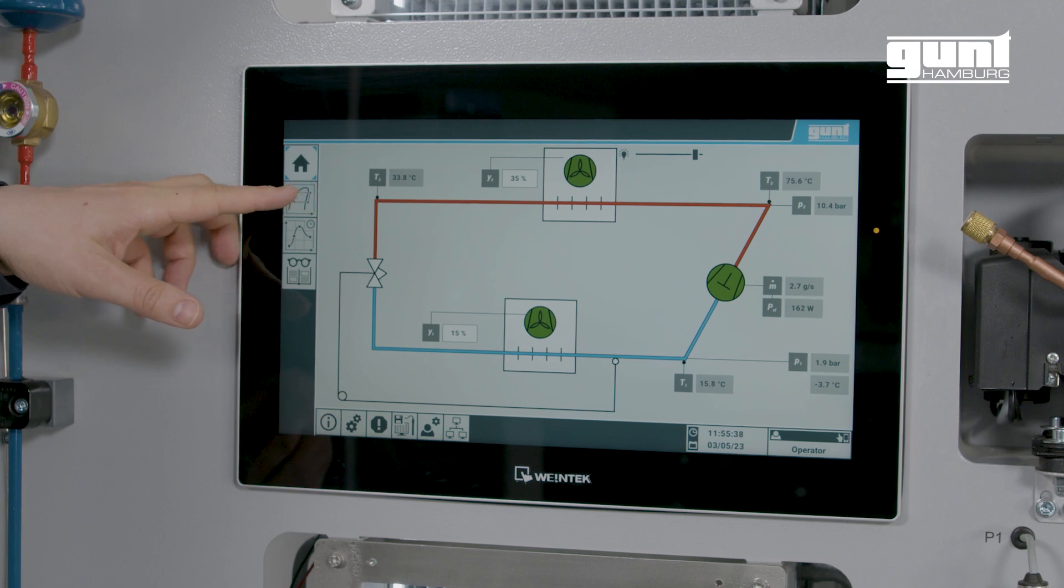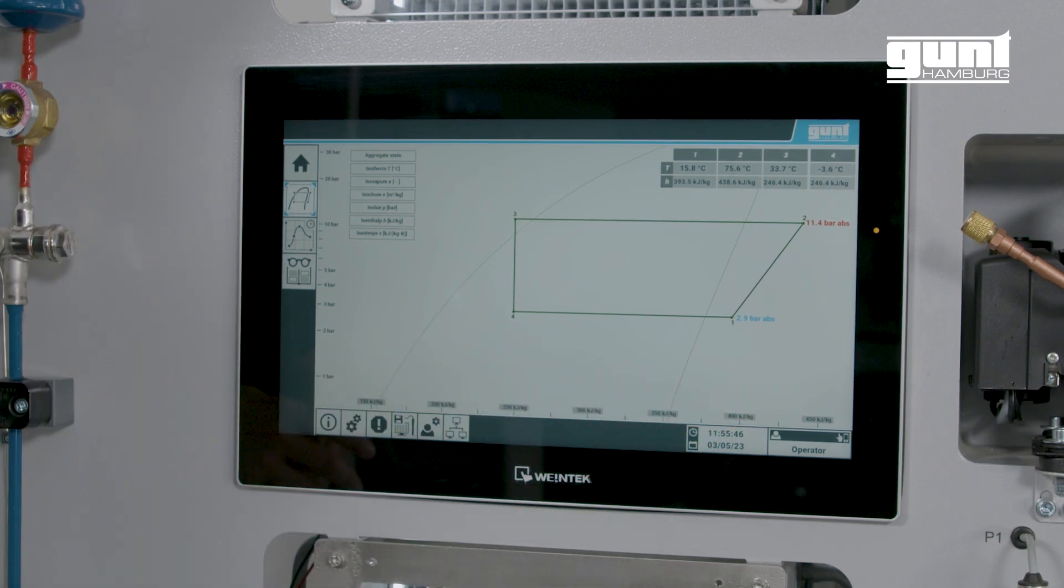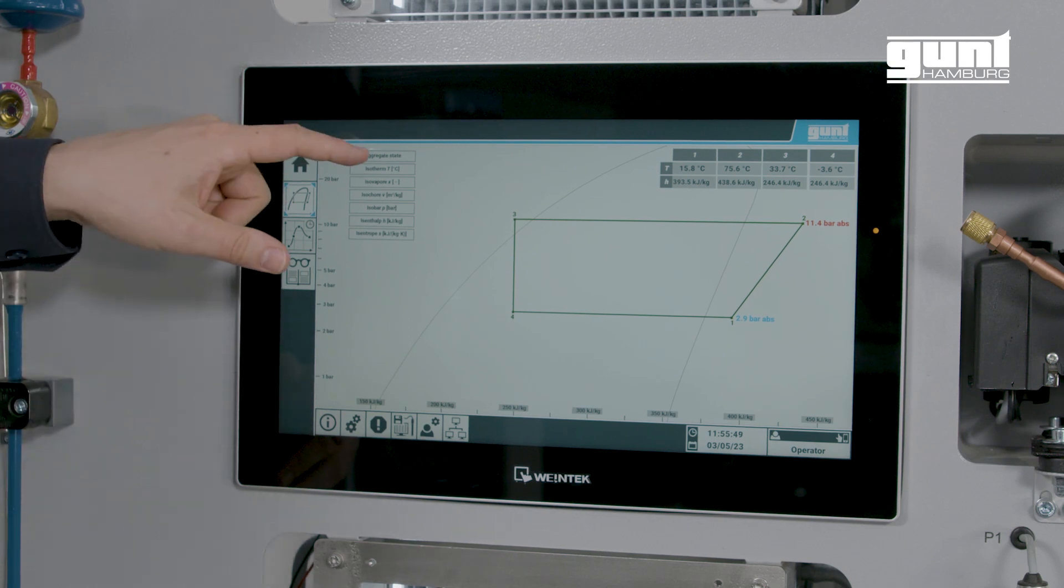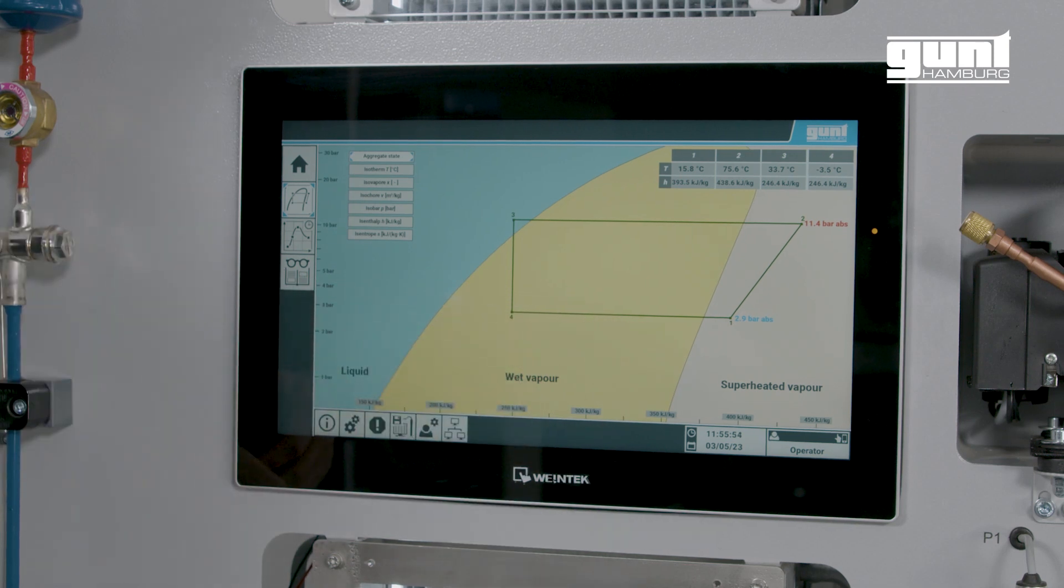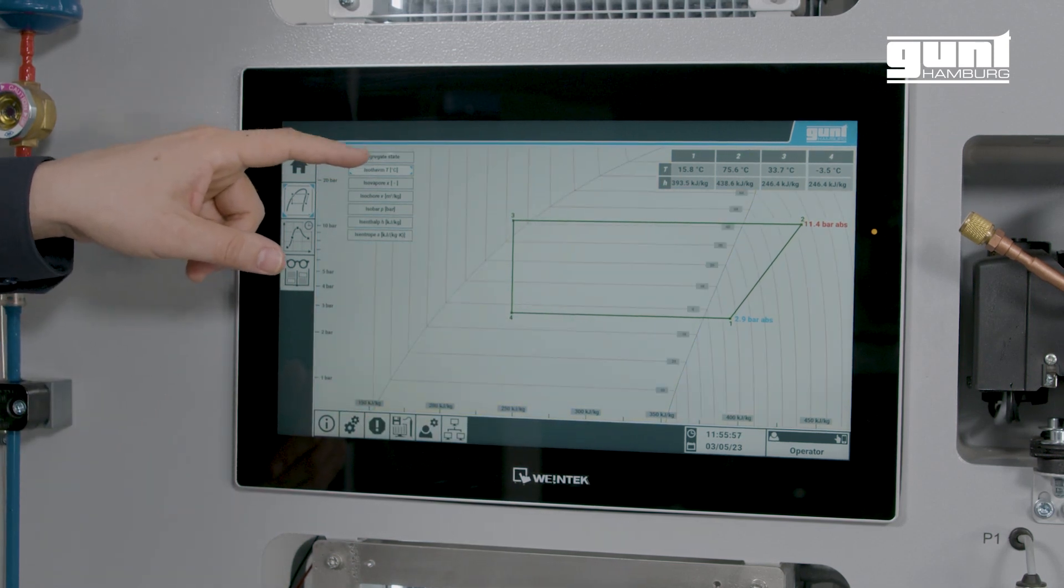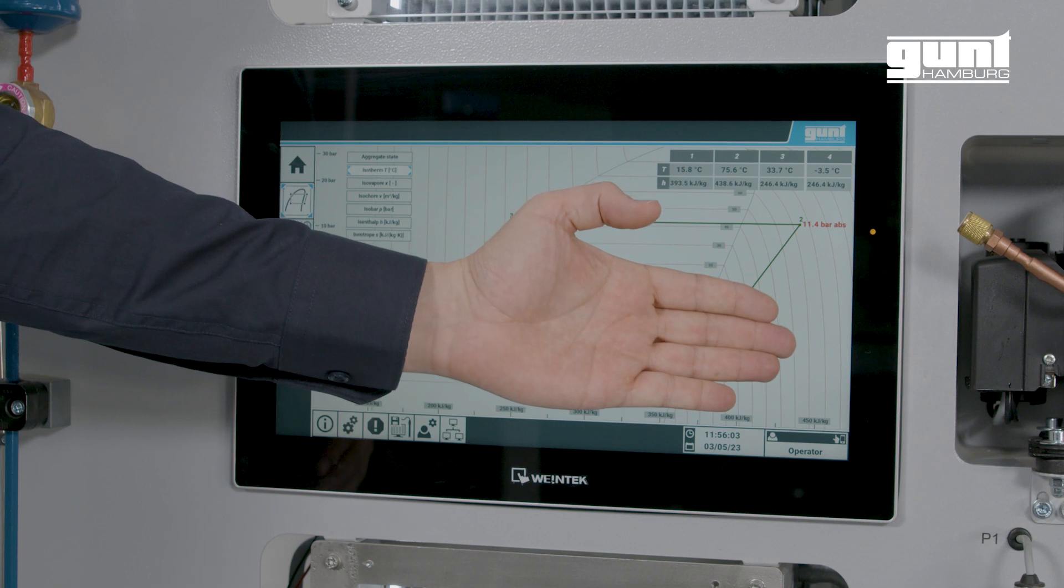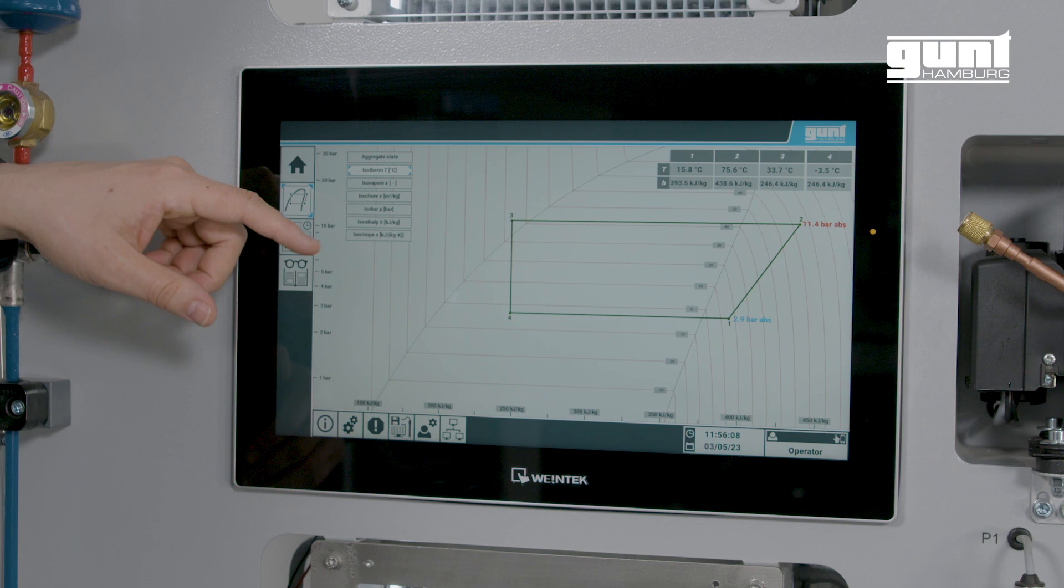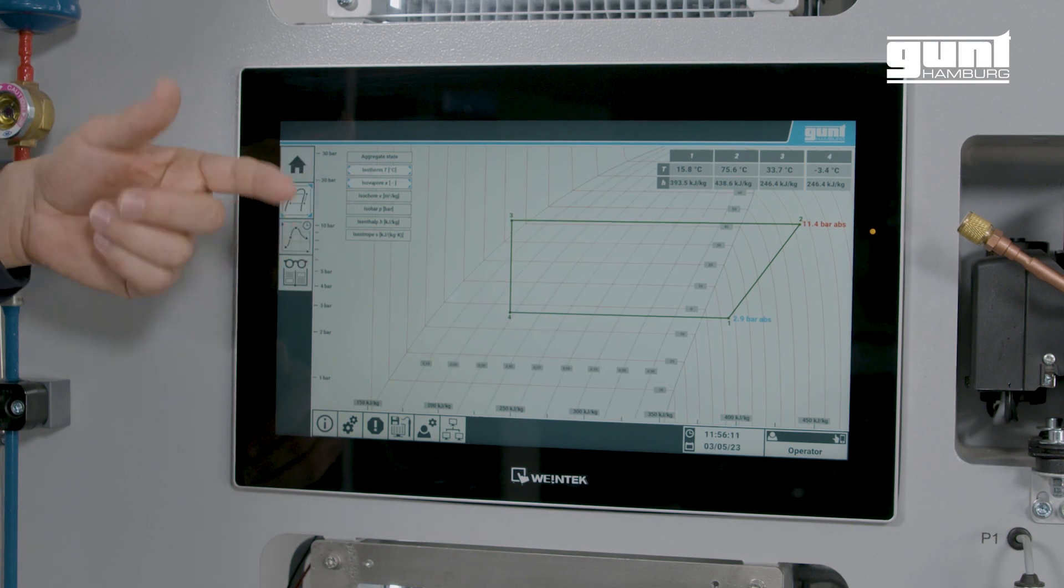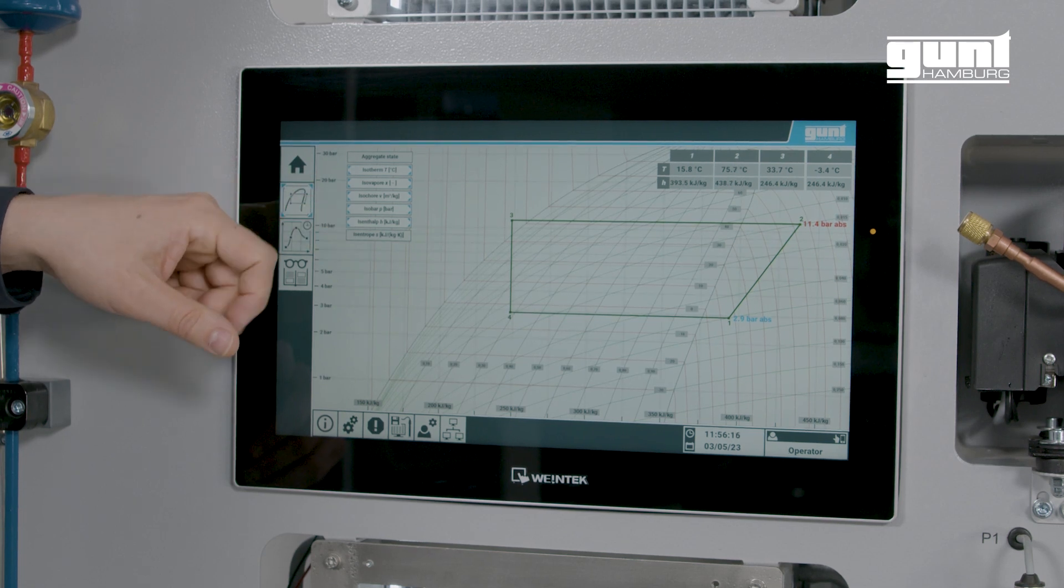And on the next page we have the log p-h diagram. Here the thermodynamic cycle of the actual operating condition is shown in real time. The specific enthalpy can be read off directly. And for a low threshold start it is advisable to query the aggregate states. Then we can continue with the thermodynamic changes of state where one variable is always constant, for example the isotherms. We can follow the same approach for all other thermodynamic state changes as well, allowing us to explore how different variables behave when one of them is held constant.